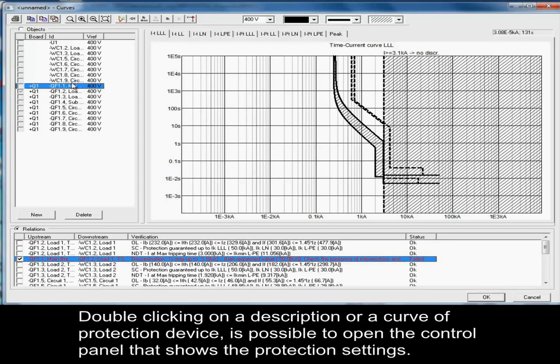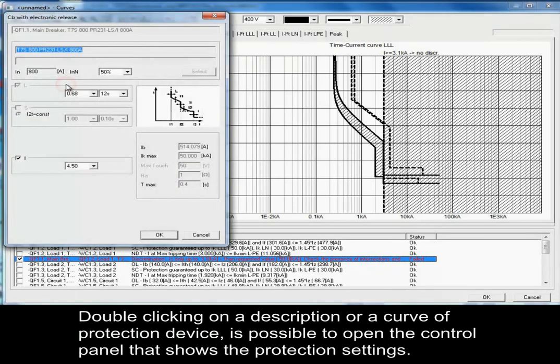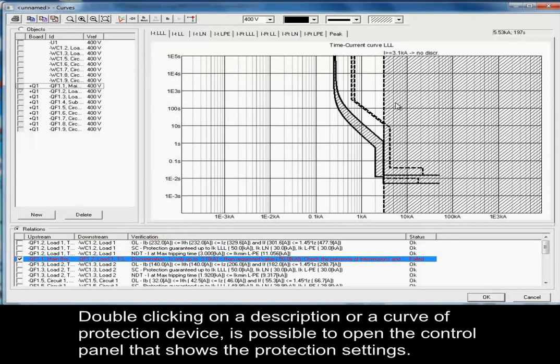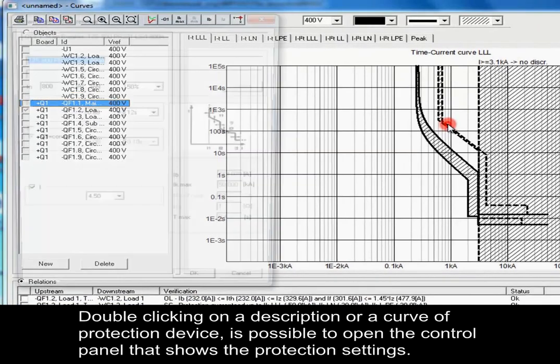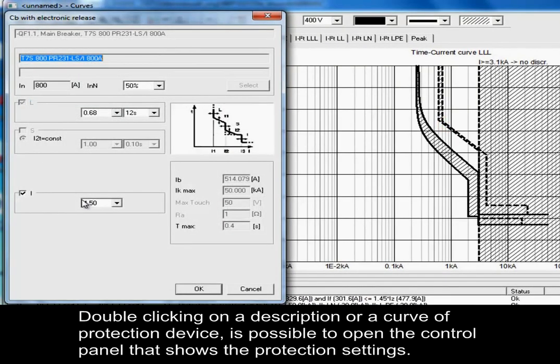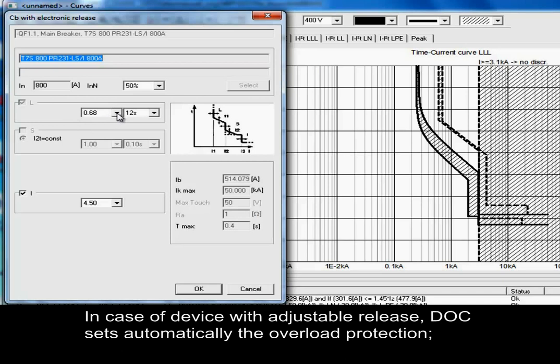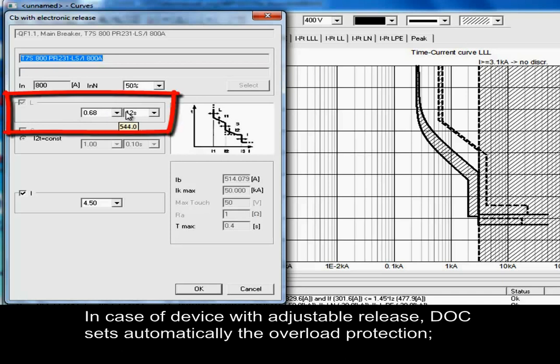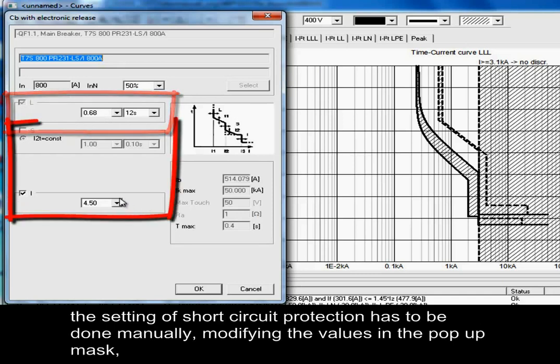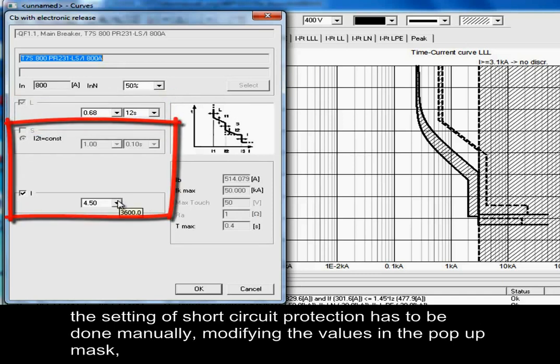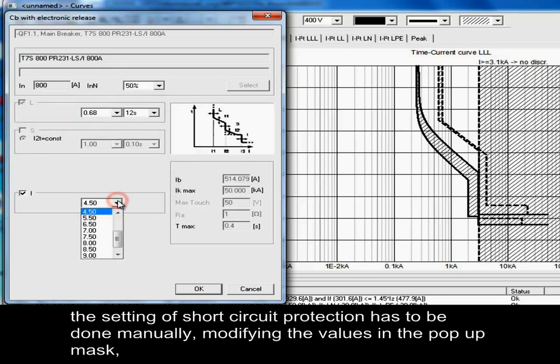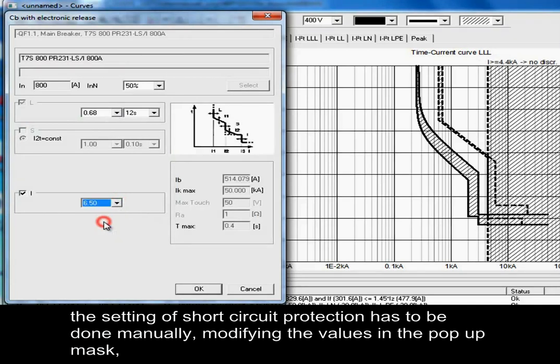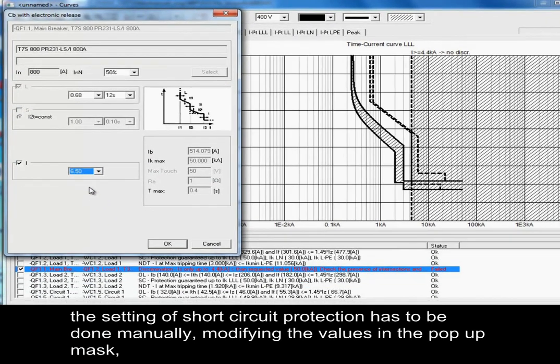Double-clicking on a description or a curve of a protection device, it is possible to open the control panel that shows the protection settings. In case of device with adjustable release, DOC sets automatically the overload protection. The setting of short-circuit protection has to be done manually, modifying the values in the pop-up mask.